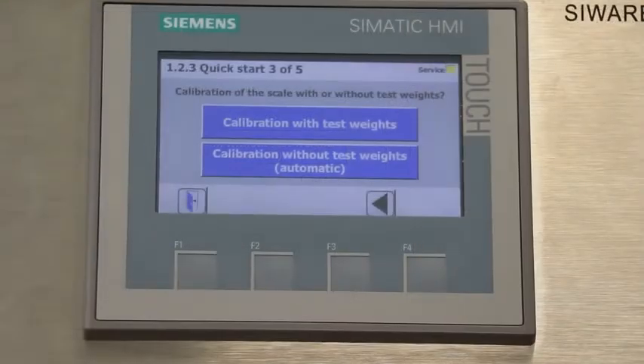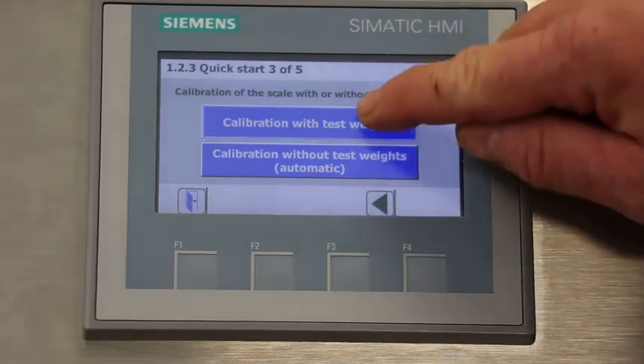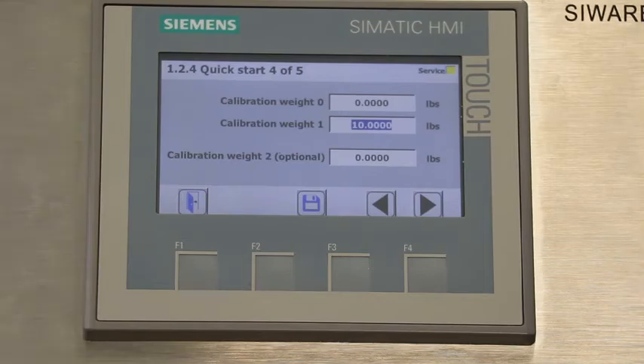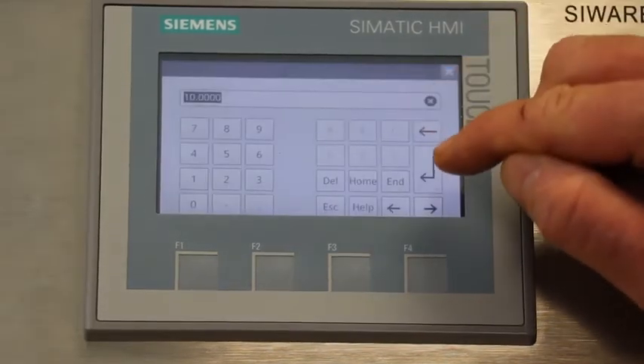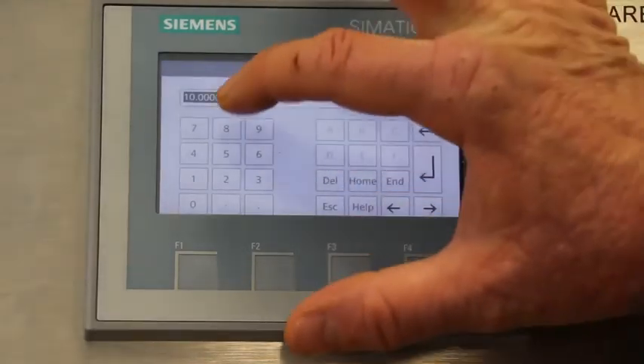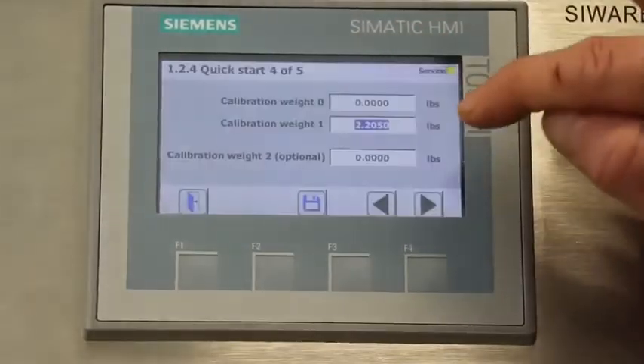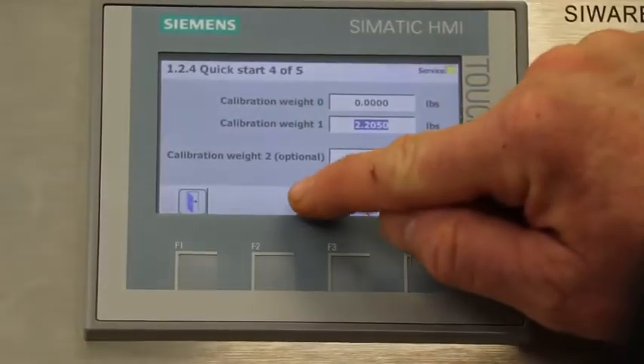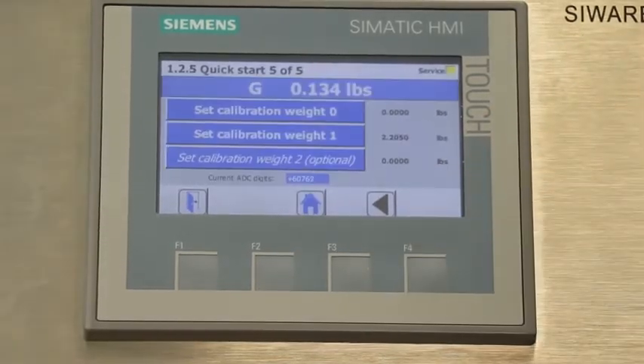The next screen will ask you if you want to calibrate with calibration weights or do you want to enter the information from the load cell. We'll enter calibration weights this time. So we'll select that. The next screen will ask you for 2 calibration points. The first calibration point will almost always be 0. And then the second calibration point will be the weight of your calibration weight. In this case, we're using a 1 kg weight. So we'll enter 2.205 pounds. We'll save that and move to the next screen.